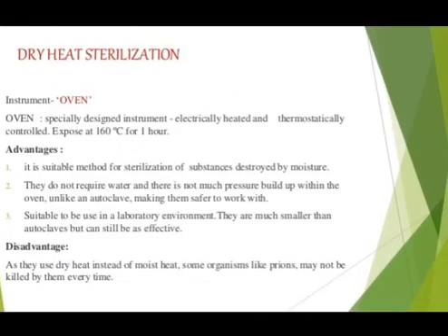The first method among the physical methods is dry heat sterilization. The instrument we use is the oven. They are specially designed instruments, electrically heated and thermostatically controlled, exposed at 160 degrees Celsius for 1 hour. Advantages: it is a suitable method for sterilization of substances destroyed by moisture.